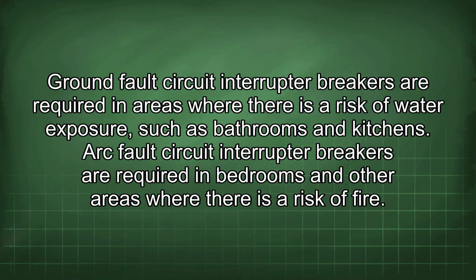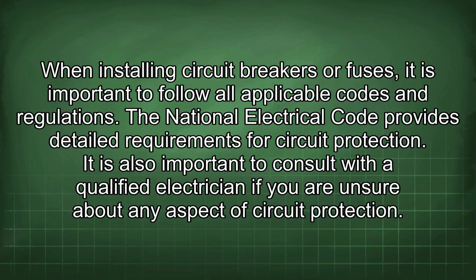Ground fault circuit interrupter breakers are required in areas where there is a risk of water exposure, such as bathrooms and kitchens. Arc fault circuit interrupter breakers are required in bedrooms and other areas where there is a risk of fire. When installing circuit breakers or fuses, it is important to follow all applicable codes and regulations. The National Electrical Code provides detailed requirements for circuit protection. It is also important to consult with a qualified electrician if you are unsure about any aspect of circuit protection.